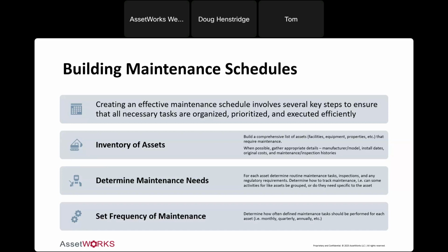Whereas in, say, the public library, that's only open 6 days a week and only open from, say, 9 to 6 on those 6 days, maybe doesn't need that same level of service that the unit at the 911 center needs. So I can build my schedule around that to know that, yeah, I can check this one maybe every other month or quarterly versus monthly. So these are considerations to make when planning, especially when planning with the resources you have available.